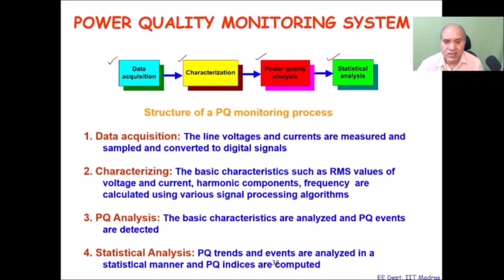So at each stage there are some functions. For example, at data acquisition stage we get all the parameters of voltage and current through proper transducers or sensors, converted to their digital signals. And then there is characterization. Based on these values, we characterize these parameters in terms of the RMS values, peak values, frequency, and so on, using various signal processing algorithms. And third is the analysis part. Once the characteristics of these parameters are available, then we can go for analysis, and also we do the statistical analysis, offline analysis. The trends of the PQ quantities like voltage and current variations, THD variations, are analyzed in a statistical manner, and the PQ indices are computed.